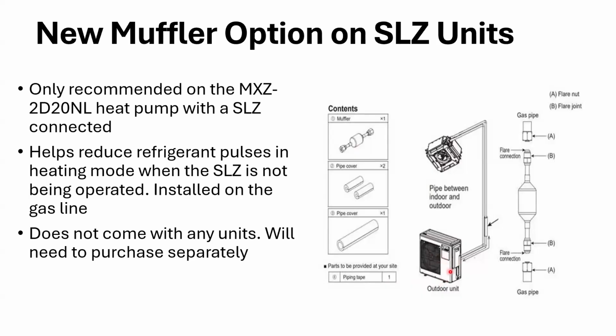So here's the outdoor unit, and you're probably not going to have room to put it between the outdoor unit and the wall. So in the vertical portion is where they're putting that there. Flared connections. So line set, right? It's already flared on that usually. If not, then I mean you're flaring on each end of that. So that's how it's going to be installed in that situation.